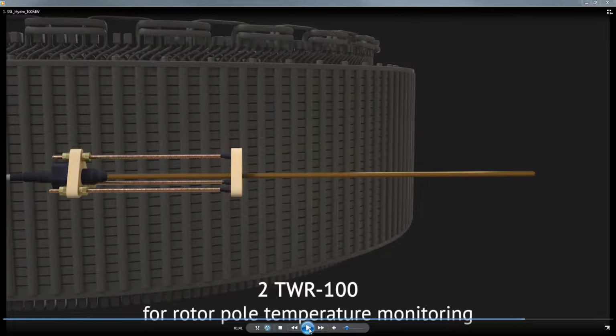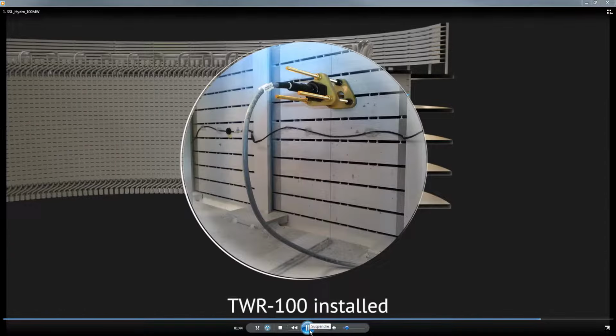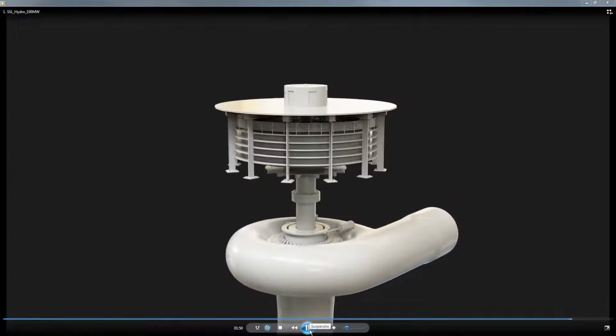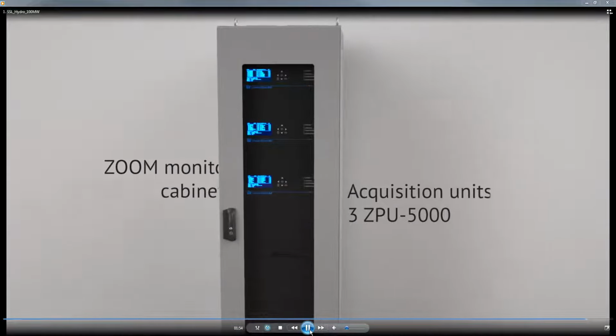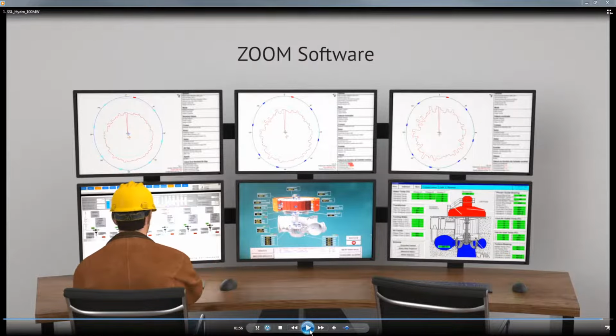And finally, we will put some ThermaWatch rotor sensors, infrared sensors that are looking towards the rotor through the ventilation holes, and are able to tell us if we have temperature issues with the poles while the unit is in operation. I have an example here. Okay, so for hydro generators, that's basically the recommended system. We have Zoom cabinets with electronics and corresponding software that can communicate with our equipment, retrieve all the data, and send the data to your SCADA system. We can also get information from your SCADA system into our system, making it a fully integrated system.